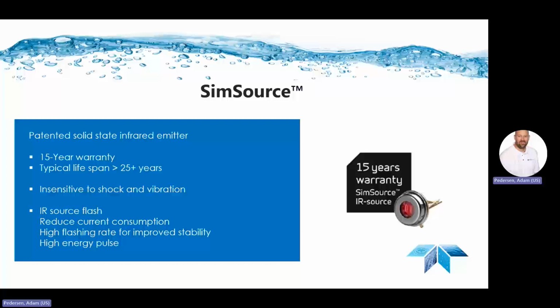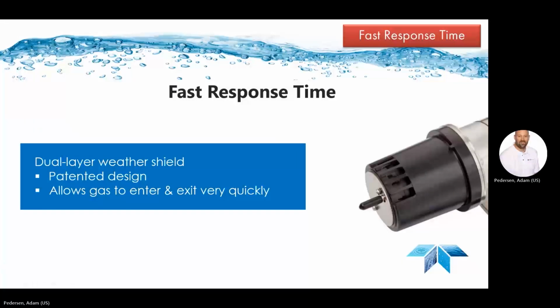So again, like we talked about, one of the best warranties on the market, can last in some really rough and rugged environments. The GD10P also excels with the ultra-fast times responding to gas exposures in only a few seconds. And so the patented dual-layer weather shield design allows gas to rapidly enter and exit the measurement chamber. Since the weather shield contains no sinters or mechanical filters, it provides the same fast response under any conditions. Response time can be adjusted through a HART handheld, and so we'll talk about those response times here on the next slide.